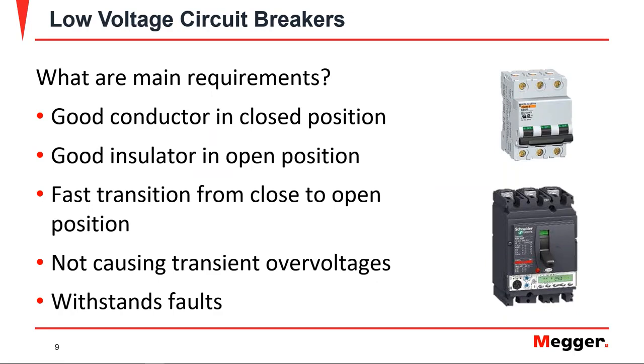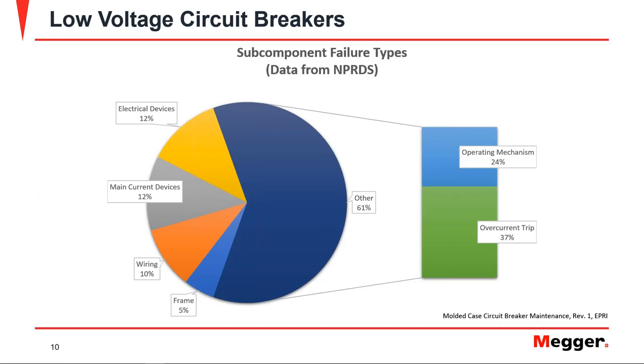And speaking of which, on the other hand, how do these elements of the system fail? The mechanical parts are prone to corrosion, fatigue, broken parts, misalignments, hardened grease, dust, or low temperatures. The current carrying parts, the conductors, are prone to loose connections, thermal overstressing, or short-circuit events. In the other elements, we can have miswired sensors, incorrect settings, or solid-state devices, like electronic trip units, that can be dead or shorted or programmed incorrectly.